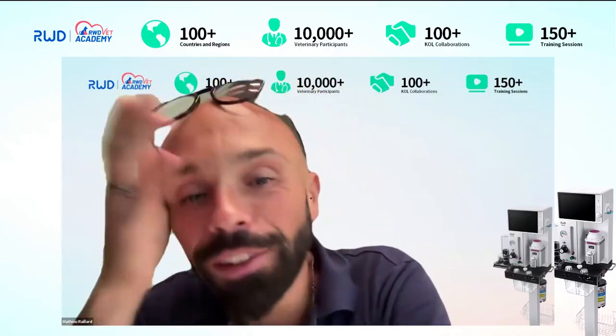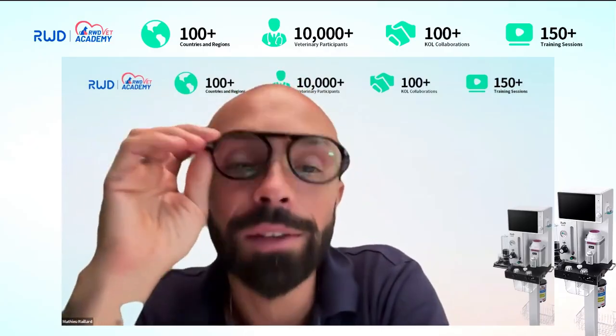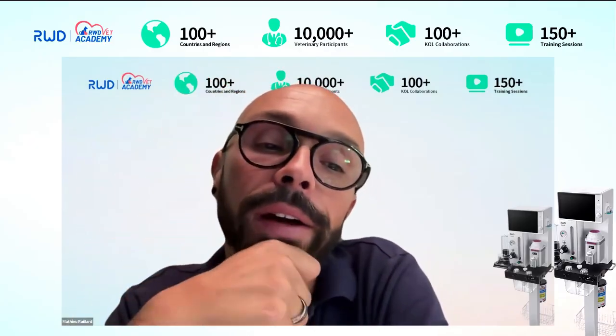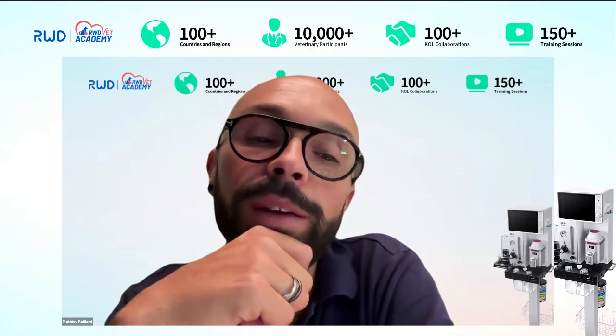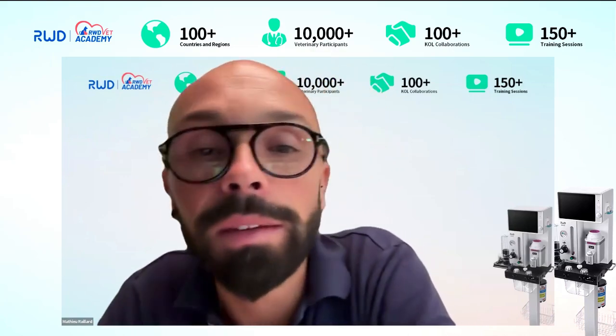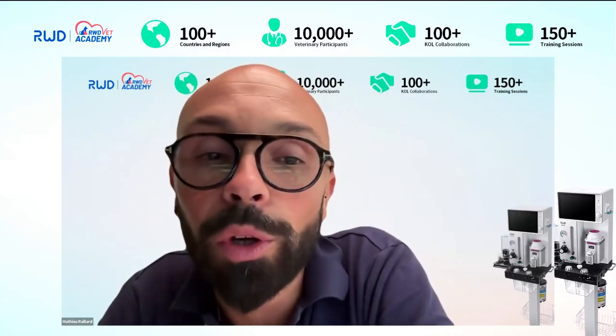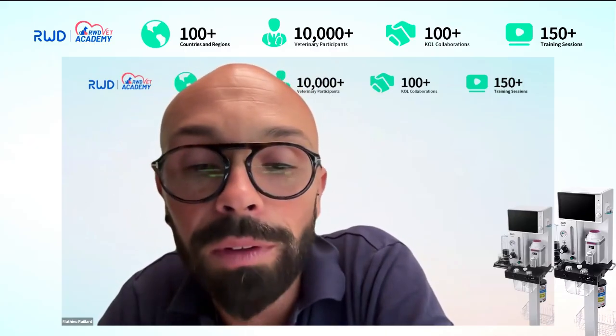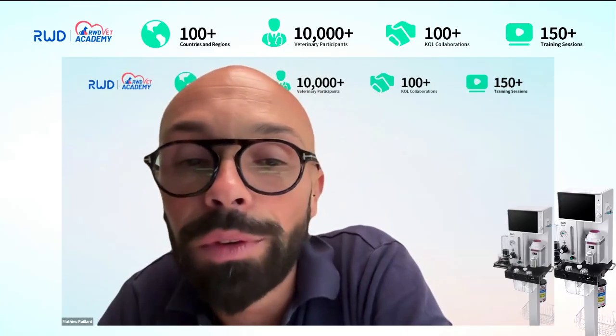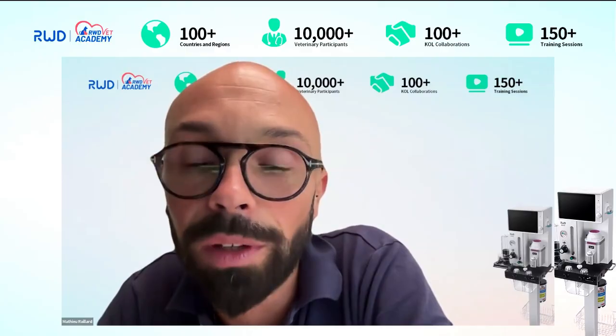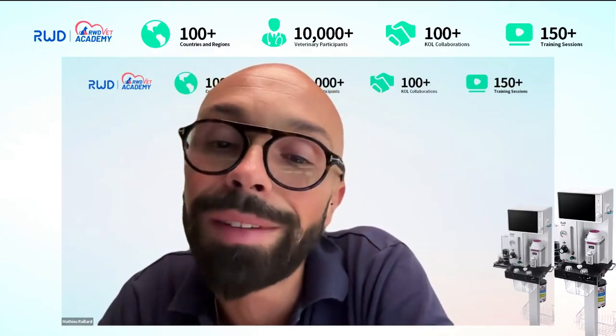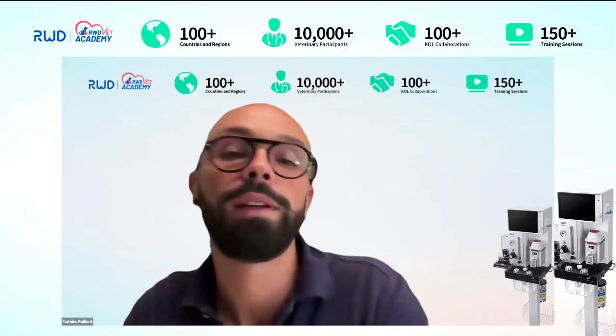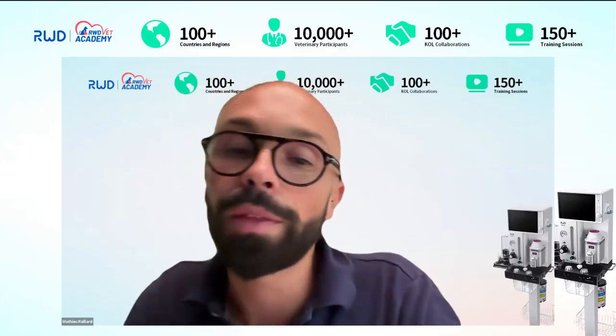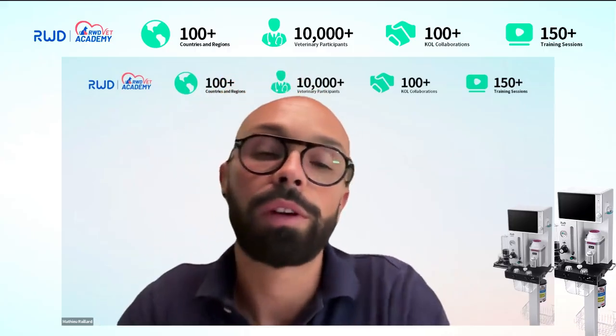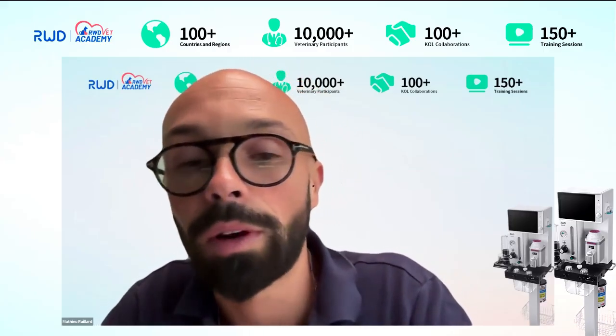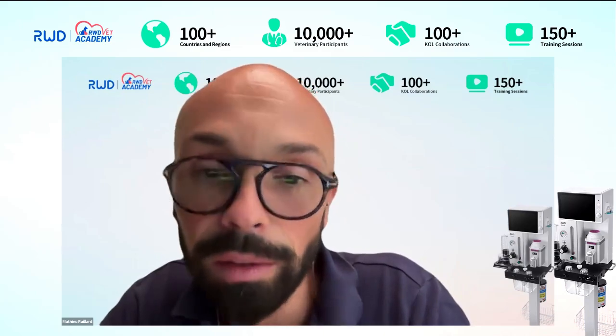The fresh gas flow has the potential to influence the tidal volume on certain ventilators. It really depends on the arrangement, on the type of ventilator. It's equipment dependent, and it depends on where your common gas outlet and your fresh gas flow get to the circle breathing system, assuming that you are using a circle breathing system. So yes, it's possible. It's not the case in all ventilators, but it is in some, and that depends on where your fresh gas flow is connected in relation to your reservoir bag or your ventilator. So yes, it's totally possible.